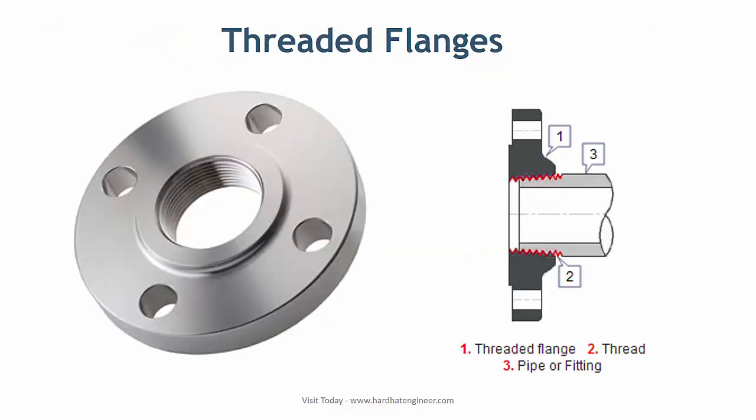Threaded flanges are also known as screwed flanges. They have a thread inside the flange bore which fits on the pipe with a matching male thread on the pipe. This type of joint connection is speedy and simple but not suitable for high pressure and temperature applications. Threaded flanges are mostly used in utility service such as air and water.